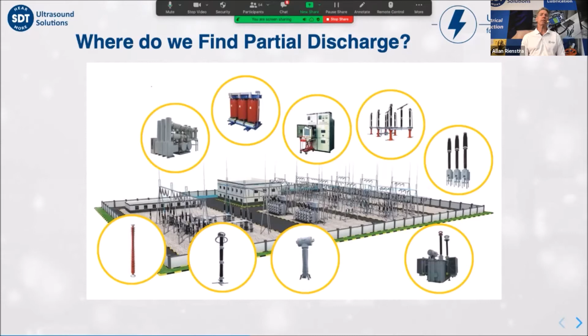Where do we find PD? Well, the answer is anywhere and everywhere. You can find partial discharge activity in all types of high voltage, medium voltage, and even low voltage power assets, from switchgear and motor circuit controllers to transformers, overhead power lines, even underground cables. And we'll see that in some of the case studies I'm going to share with you at the end of the presentation. Partial discharge causes degradation and failures. Experience shows that PD activity is a contributory factor in over 80% of disruptive substation failures. It is the most reliable indicator of the true condition of insulation in live assets.